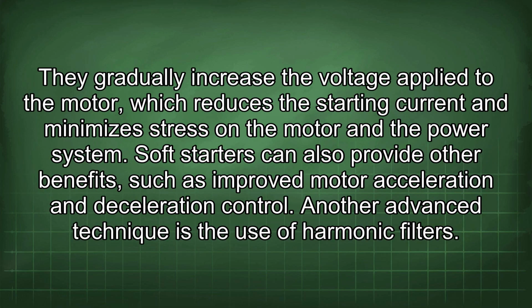They gradually increase the voltage applied to the motor, which reduces the starting current and minimizes stress on the motor and the power system. Soft starters can also provide other benefits, such as improved motor acceleration and deceleration control. Another advanced technique is the use of harmonic filters.